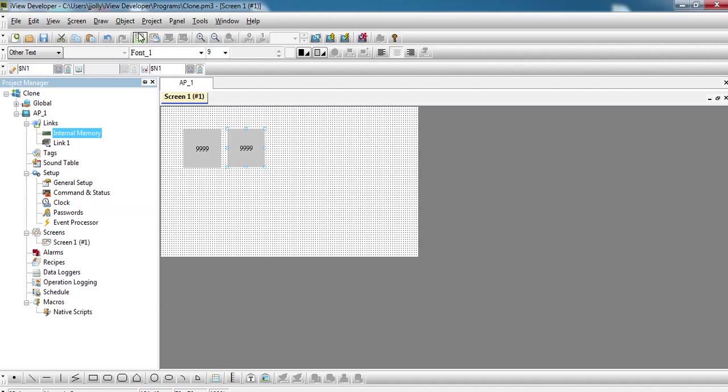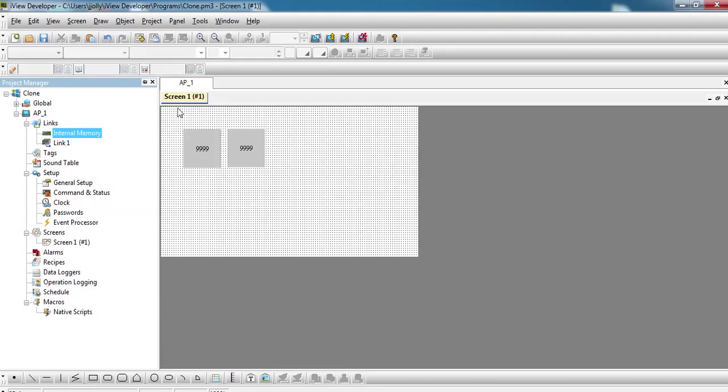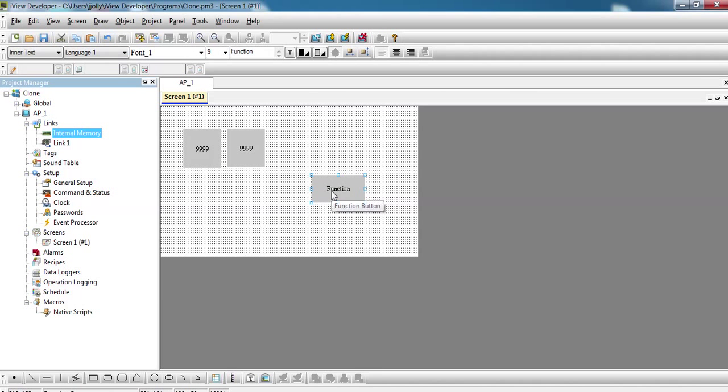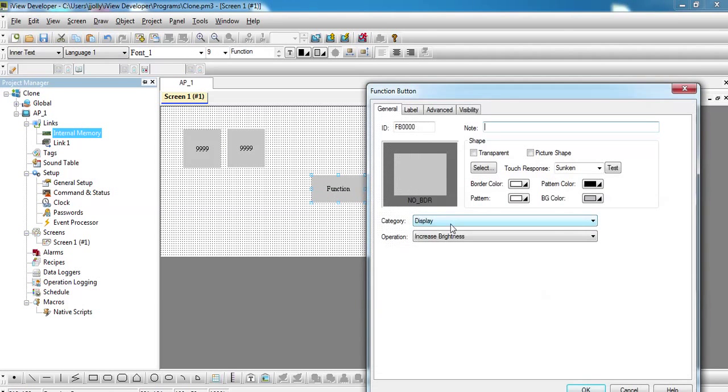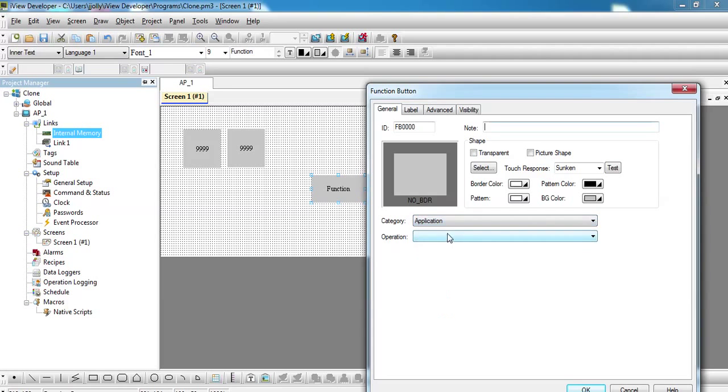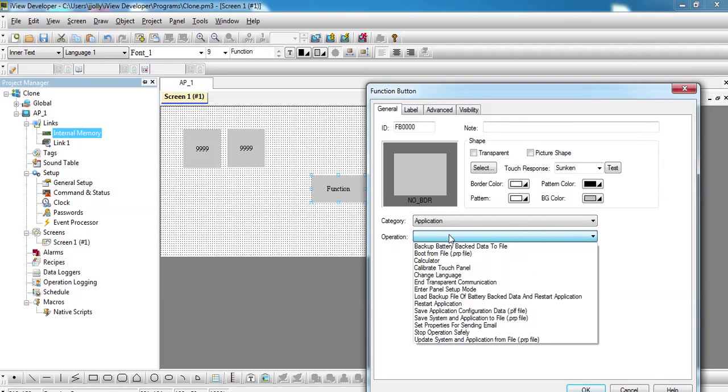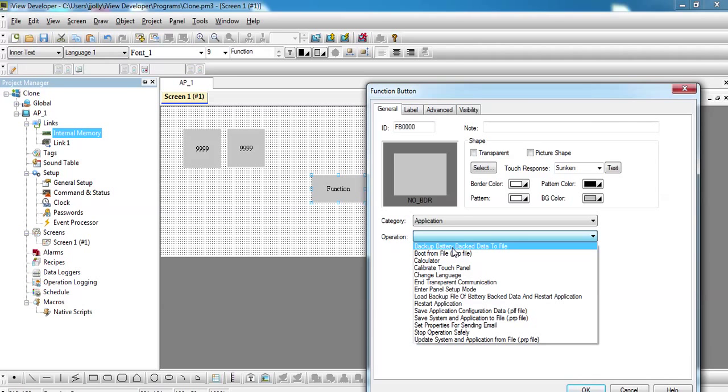The option to do is go for object function button and have it as a function. Double click on the function, go to the category, click on application, and you have two options: update system and application file from file, or load backup file. You have battery back data to file. First we need to battery backup all the data, especially the dollar n registers. Click on that.